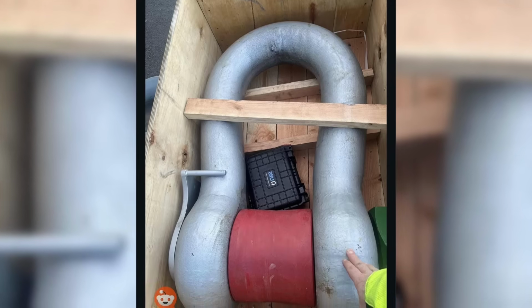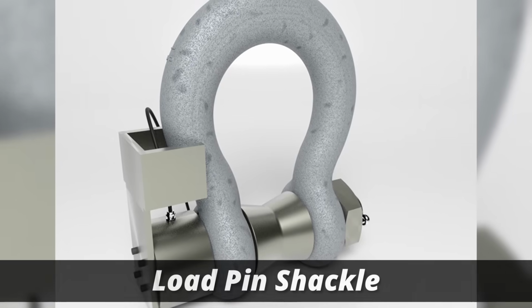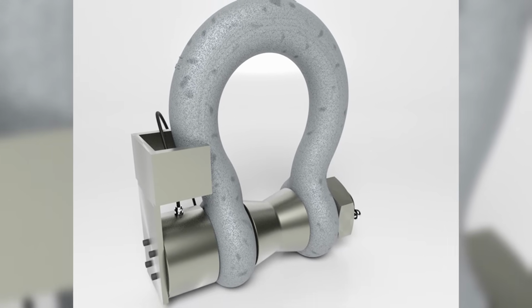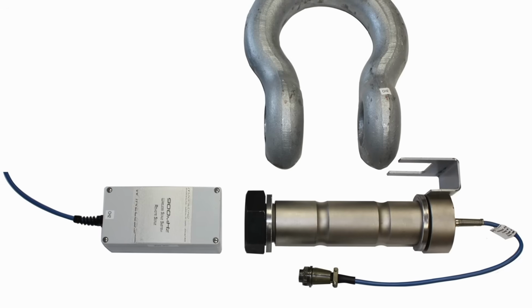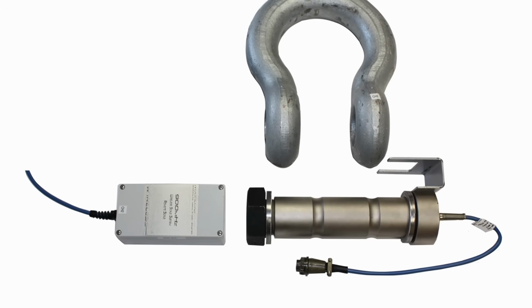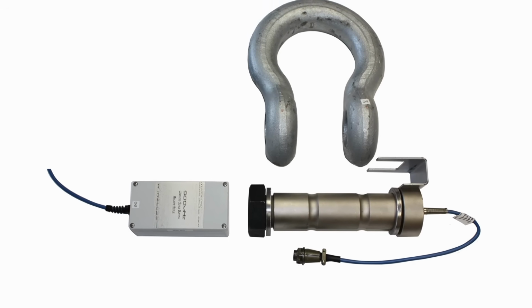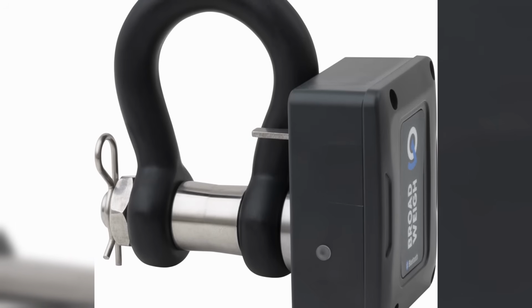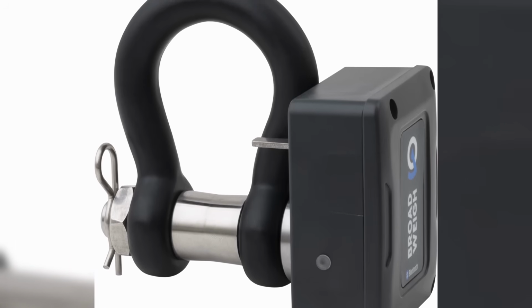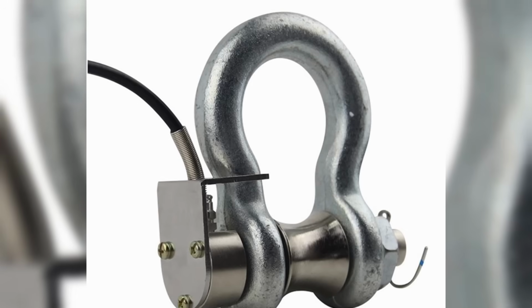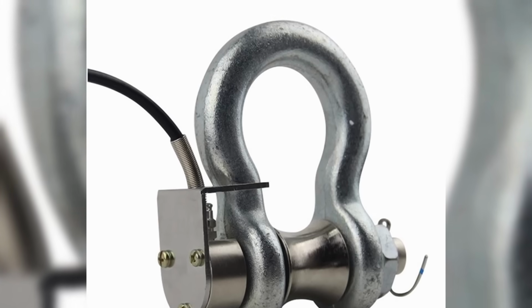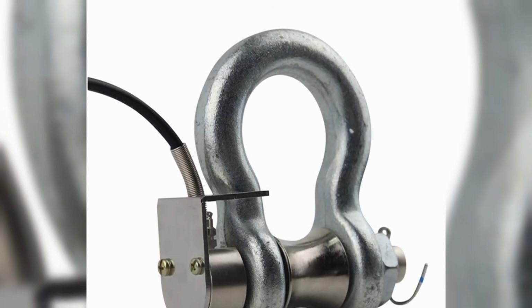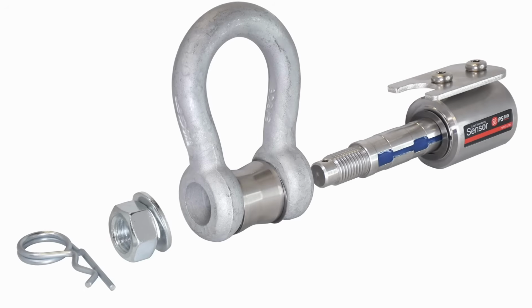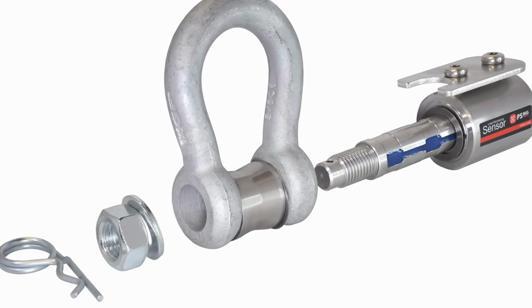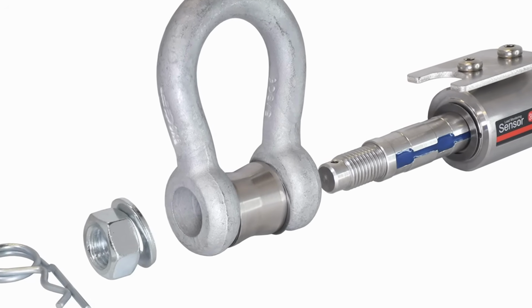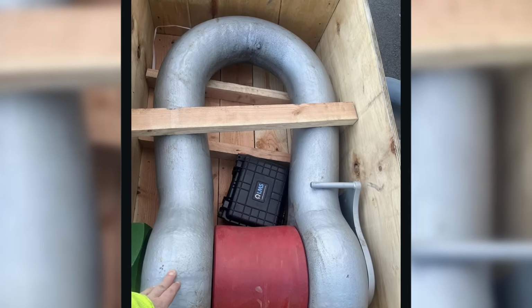This is identified as a load pin shackle. A standard shackle is a U-shaped metal piece used for connecting and securing loads in rigging and lifting operations. A load pin shackle, however, has a specialized pin that incorporates a load cell. The black box contains the electronic equipment—strain gauges, signal conditioning, display, or transmitter—connected to this load cell. This allows the shackle to not only connect a load, but also to accurately measure the tensile force or weight of the load being lifted or pulled. This data is crucial for safety, ensuring lifting equipment is not overloaded, and for verifying load weights in various industrial, maritime, and construction applications.